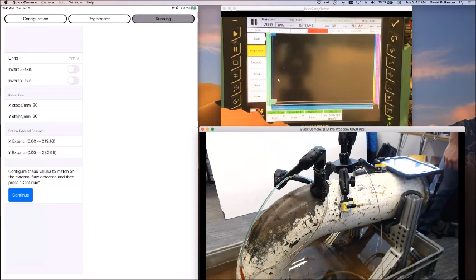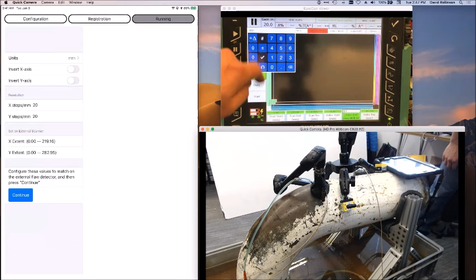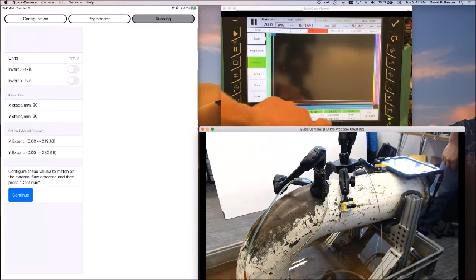Got my area set up. So I need to do 219 millimeters in X, my scan direction. I need to do 283 in Y, my index. I'll make sure my encoders are set right, 20 steps per millimeter. Basically, the system we have simulates a wheel encoder that you could send to these systems. The key thing is you just want to make sure the number here that you see in the iPad interface, in the inspector interface, matches the number that you set on the scanner. That's something that's configurable. It's a little bit different on every flaw detector, but the base feature is there.